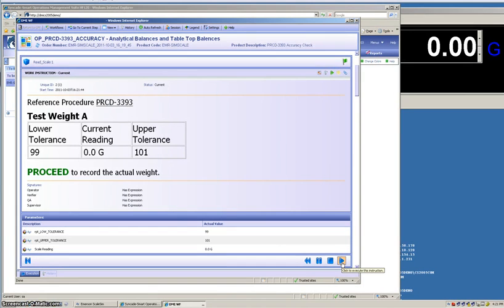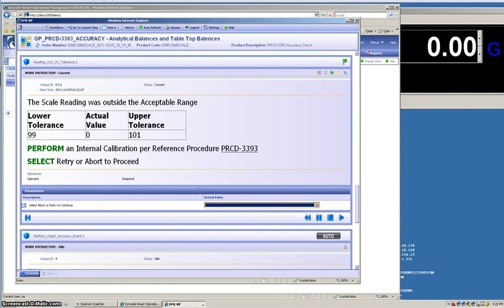Please note that this is not the correct reading, and I'm going to show you how the system will procedurally guide the operator if there's an error. We're going to record our electronic signature again and move on. This time the operator is guided and told that this reading was outside of the acceptable range. It reminds him what the lower and upper tolerances are and to perform an internal calibration per the procedure, then to retry or abort. Let's retry and continue.